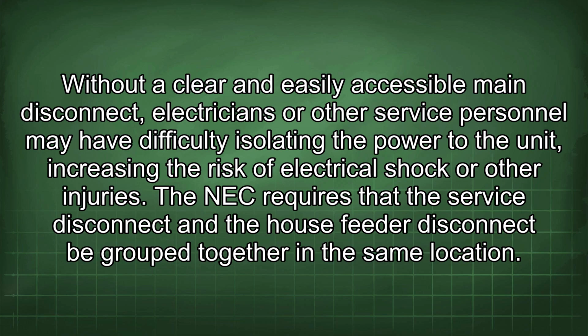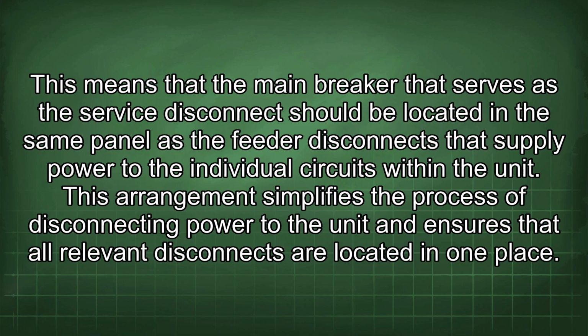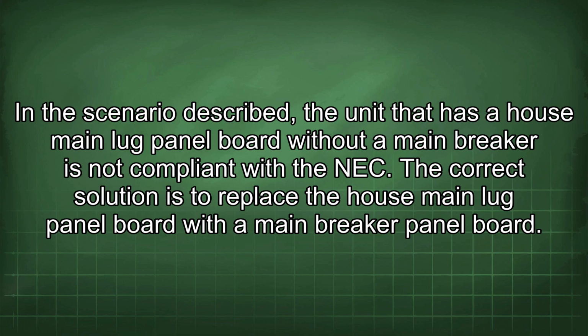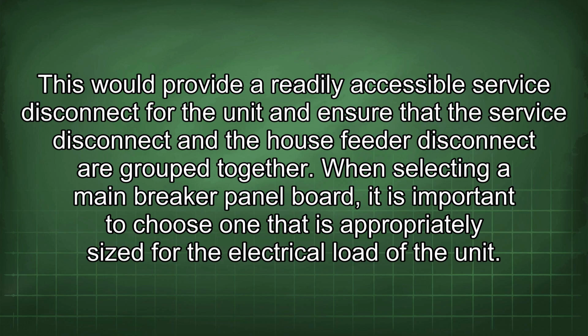The NEC requires that the service disconnect and the house feeder disconnect be grouped together in the same location. This means that the main breaker that serves as the service disconnect should be located in the same panel as the feeder disconnects that supply power to the individual circuits within the unit. This arrangement simplifies the process of disconnecting power to the unit and ensures that all relevant disconnects are located in one place. In the scenario described, the unit that has a house main lug panel board without a main breaker is not compliant with the NEC. The correct solution is to replace the house main lug panel board with a main breaker panel board. This would provide a readily accessible service disconnect for the unit and ensure that the service disconnect and the house feeder disconnect are grouped together.